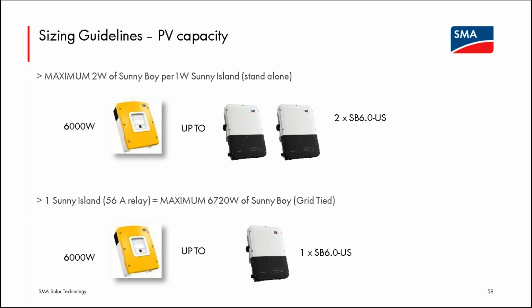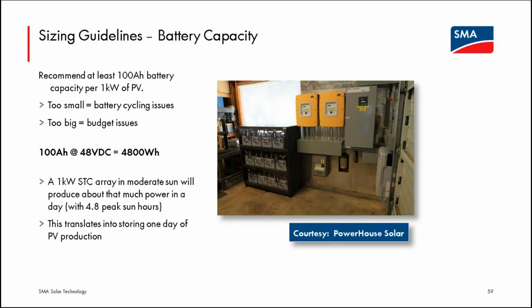The rule of thumb for off-grid systems would be no more than 2 watts of PV power per watt of Sunny Island power. You don't want the Sunny Island to have to throttle the PV system back and forth all day. Another guideline, and again, these can be changed based on local microgrid power requirements, is a minimum of 100 amp hours of battery capacity per kilowatt of PV. And you can see the math here on this slide. A 1,000 watt array should provide roughly, in a 5 peak sun hour environment, 5,000 watt hours of power. And that is roughly what it would take to charge up a 100 amp hour battery bank at 48 volts. So it's roughly a day's storage of a kilowatt of PV array in a 5 peak sun hour environment. So again, there may be reasons that this can be adjusted one way or the other, but a good rule of thumb.